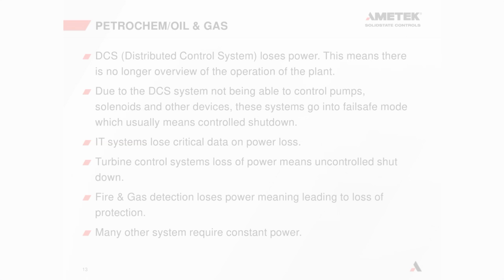If we lose sight of any of that, the turbine is going to go into a controlled shutdown, or even an uncontrolled shutdown if we lose complete power. Fire and gas detection: if we lose the ability to detect fire or gas releases, we're going to shut down the plant, because we don't know if there is a fire or gas release. The system will go to fail-safe mode and shut those systems down. There are many other systems out there that require constant, uninterrupted power.